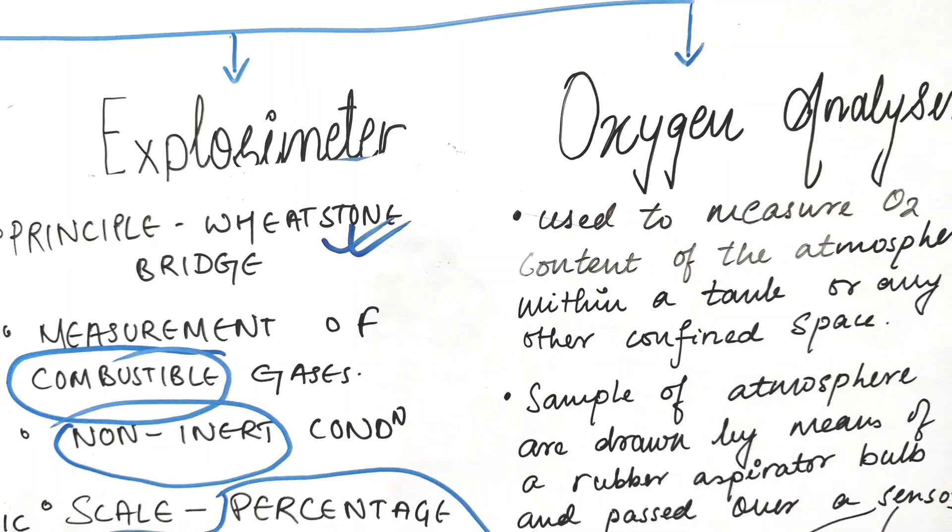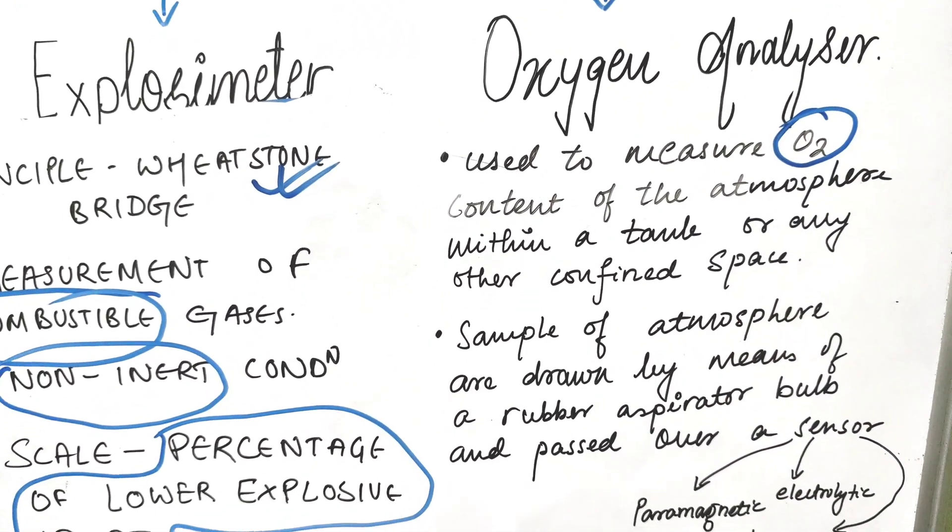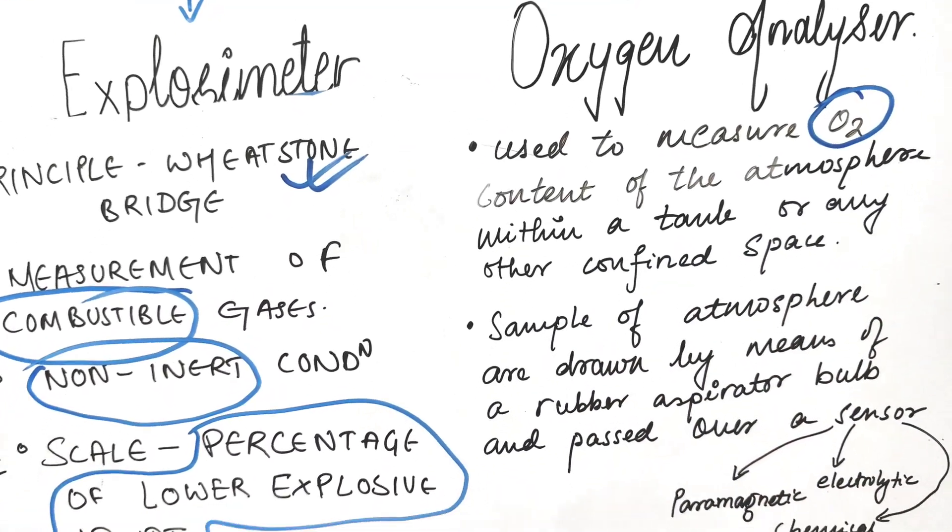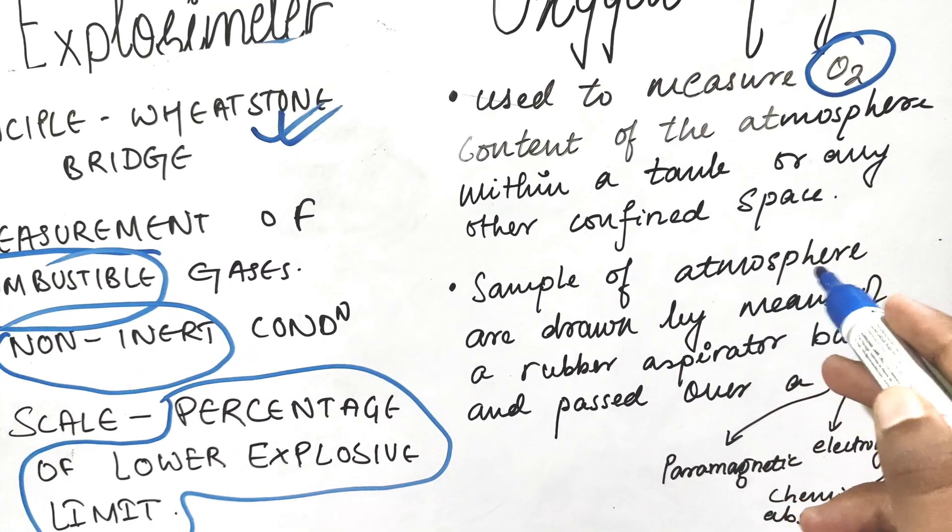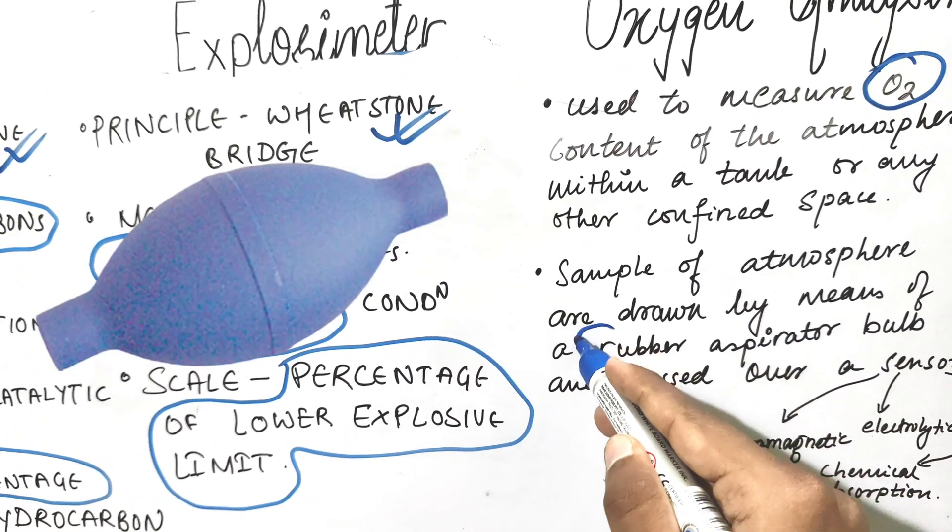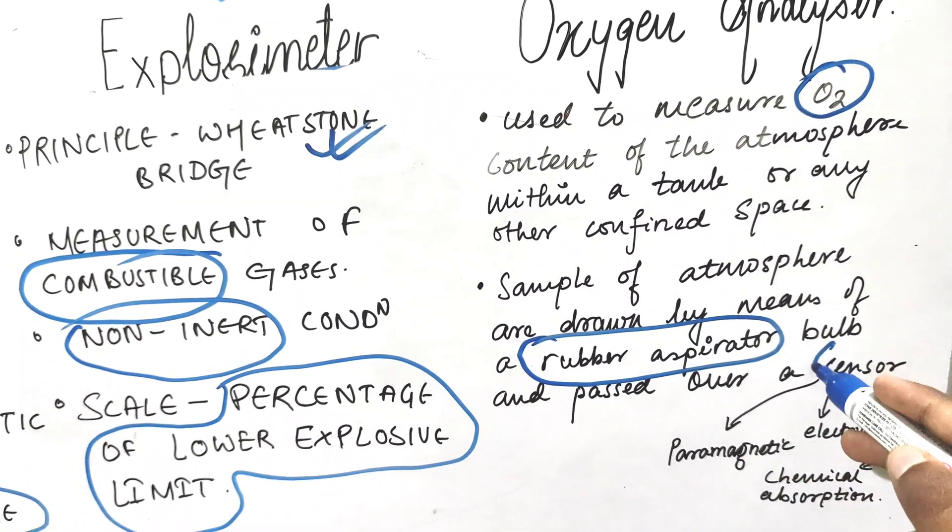Then we have oxygen analyzer. It is used to measure oxygen content of the atmosphere within the tank or any confined space. The sample of atmosphere is drawn by means of a rubber aspirator bulb and is passed over a sensor.